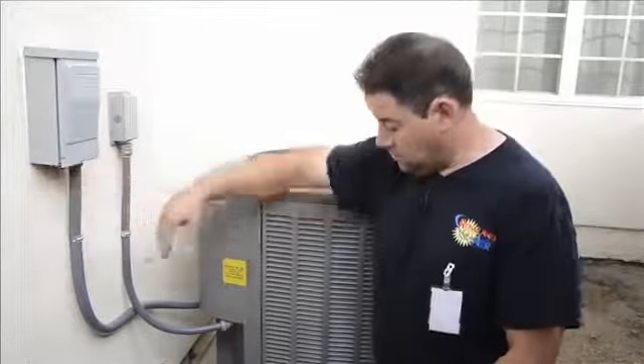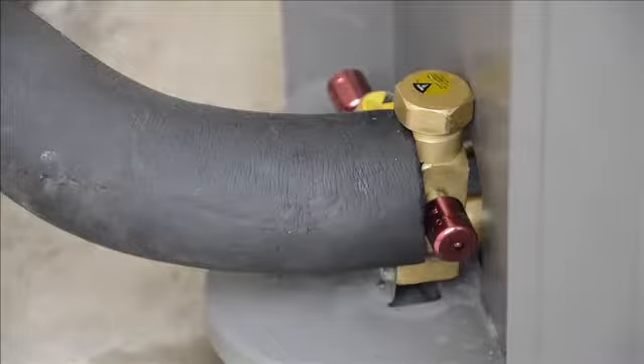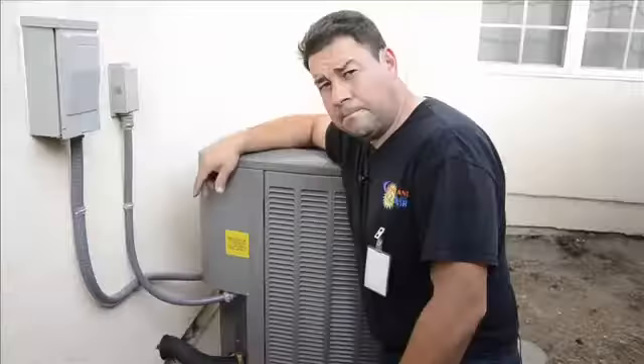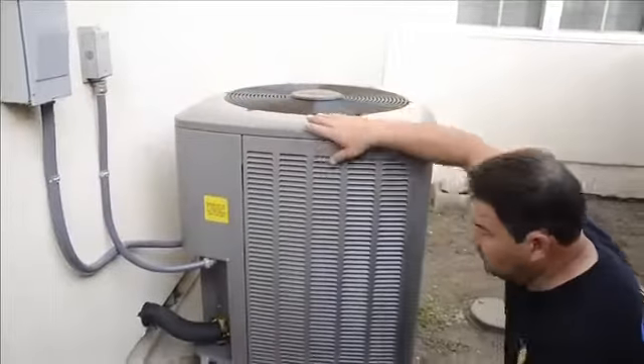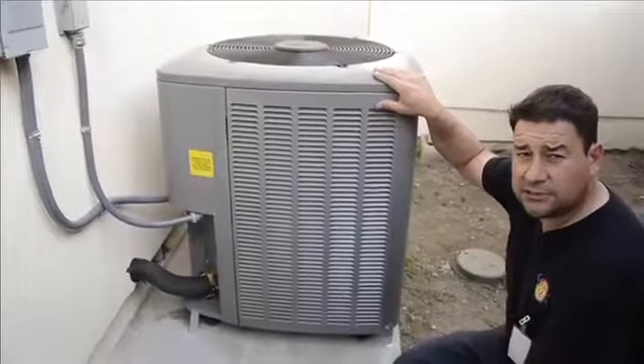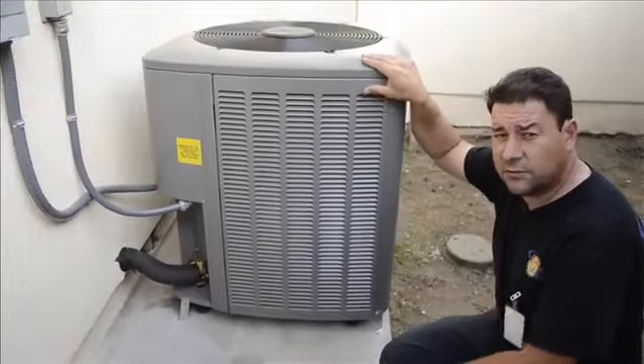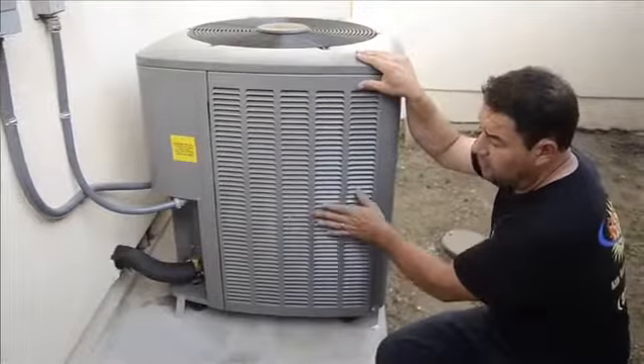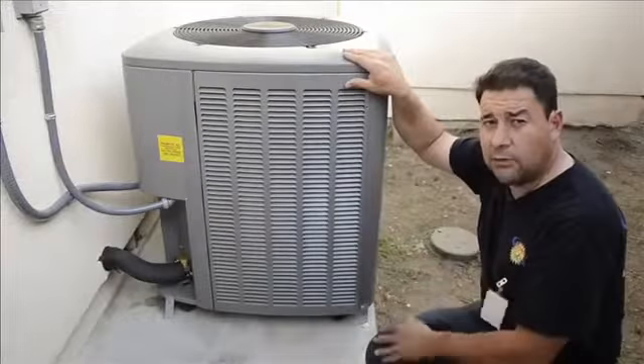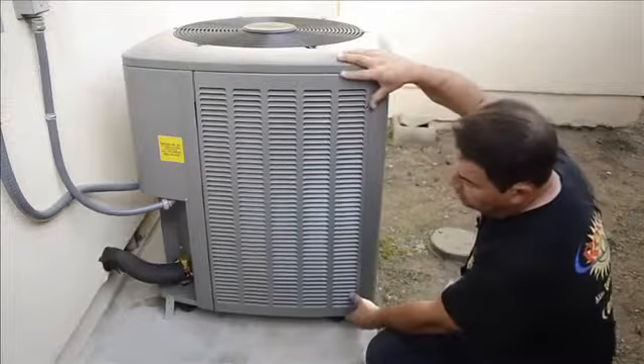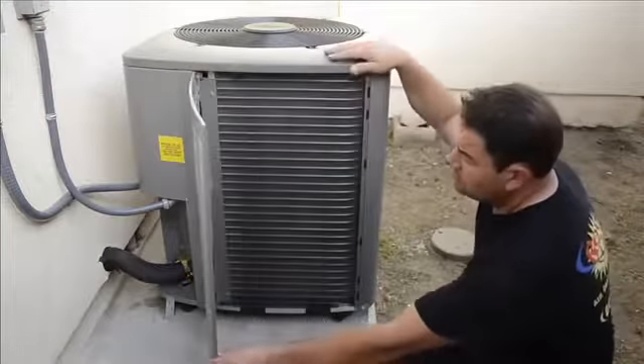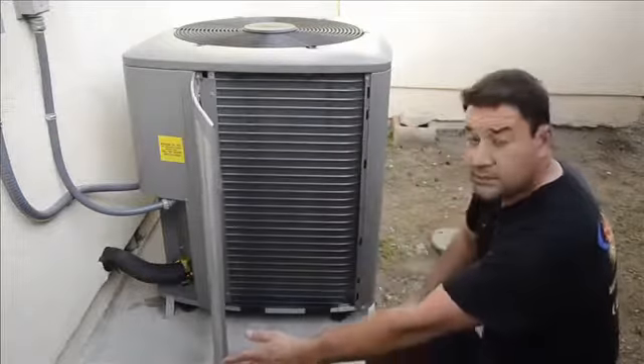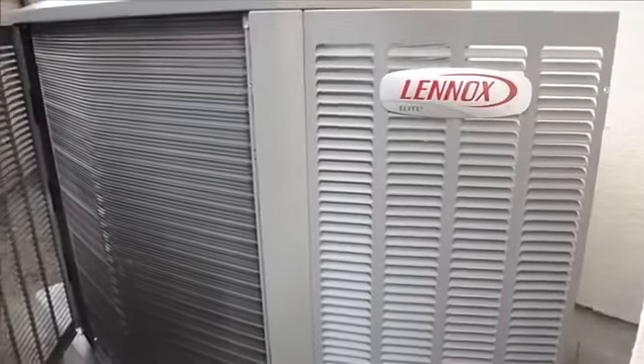And down below, you'll see the code-required Freon refrigerant locks there. And the unique thing about this XC14 condenser is when we service these condensers before the summertime, we generally have to take a hose and spray it between these louvers to get the radiator or the condensing coil. You remove a couple screws on this one, and it just swings open for proper and easy access to cleaning those condenser coils.